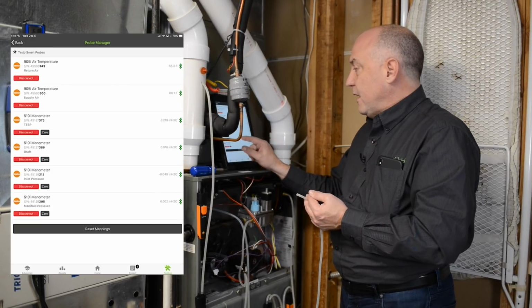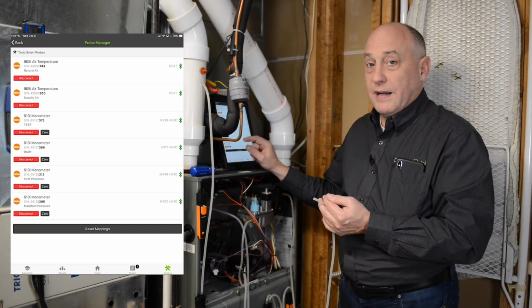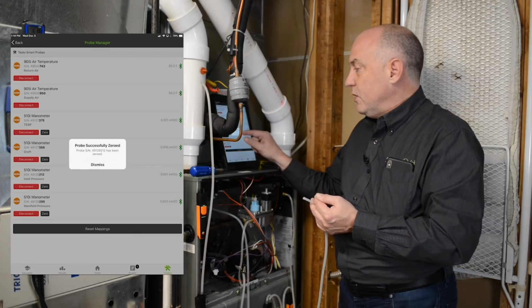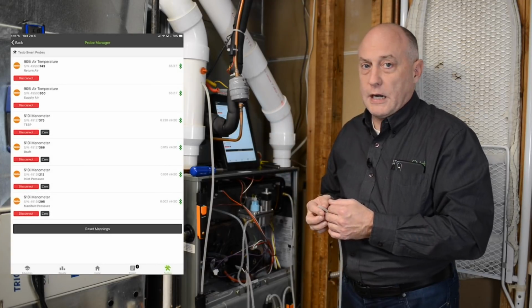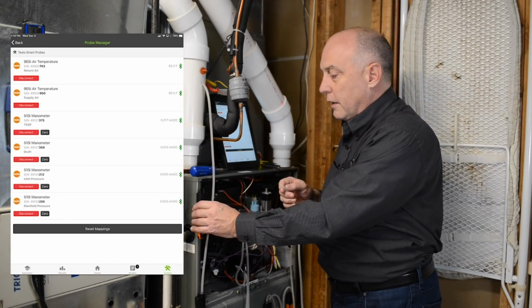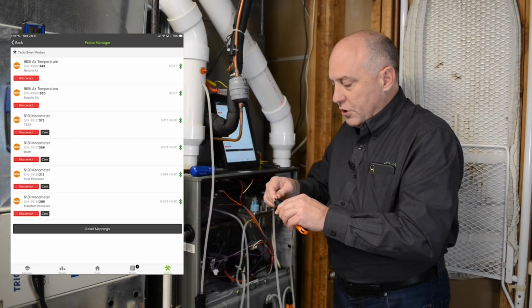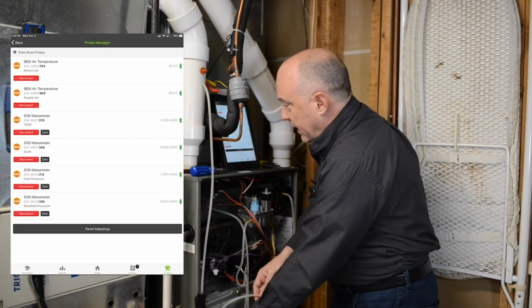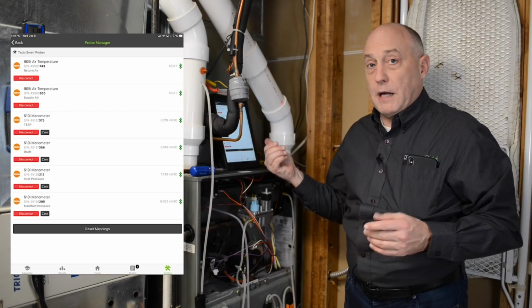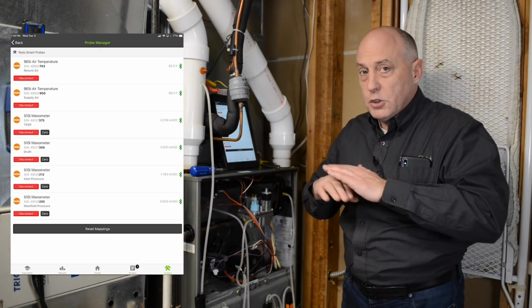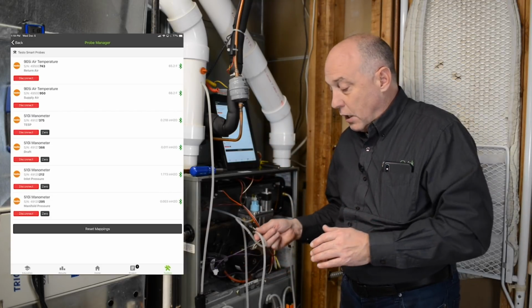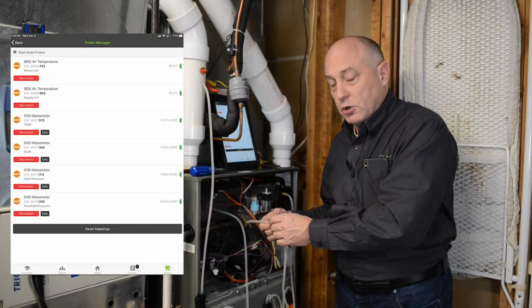So I have this disconnected on my inlet pressure. It's reading 0.049. I'll go ahead and zero that out. So it's only 0.04 of an inch of water column off, or almost 0.05 of an inch of water column. So now that's zeroed out. I'll push this hose back on here. Now, when I do push the hose on, you're going to see it's going to go up to about 1.6 inches of water column, totally normal, because I've got this capped off and it's trapping pressure in between the hose and the manometer.